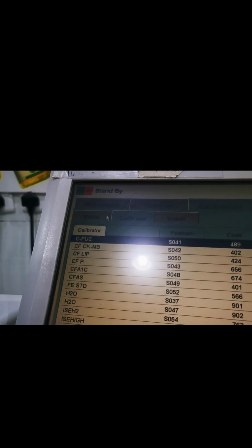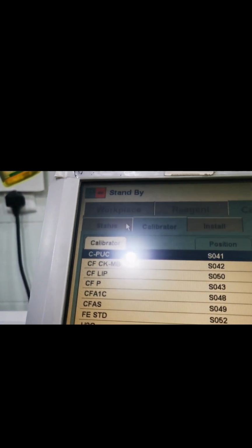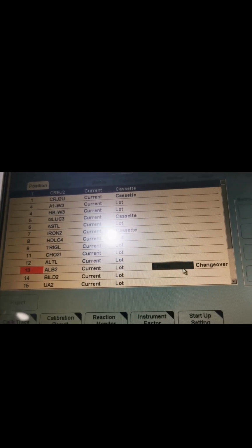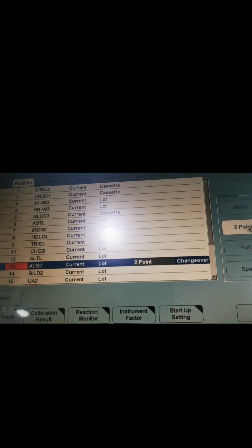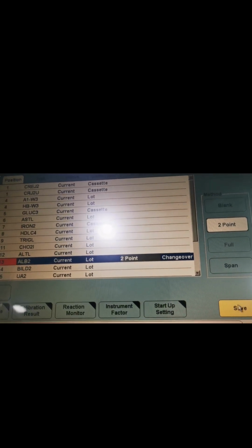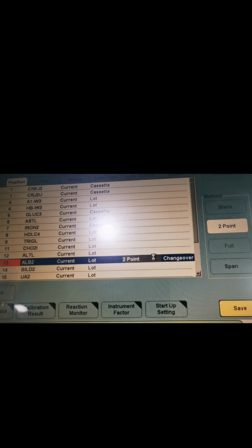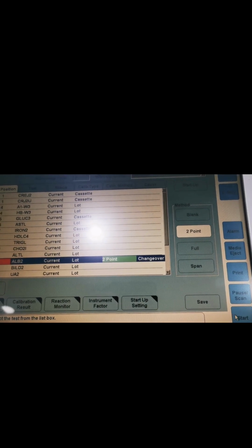Now that the control and the calibrator are already in position, we will go back to our calibration procedure. Just click calibration and then click status. We will notice that there is a red mark under ALB2, and this says 2-point changeover. Changeover means that the reagent was changed to a new one. Now we will click the method of calibration, which is 2-point, and then we will click save. By clicking save, it means that we ordered a calibration procedure here in our machine. Now press start on the lower right button and then change the position number to 1 and then press start again. Then click OK. Now the machine will start processing, preparing the calibration procedure.